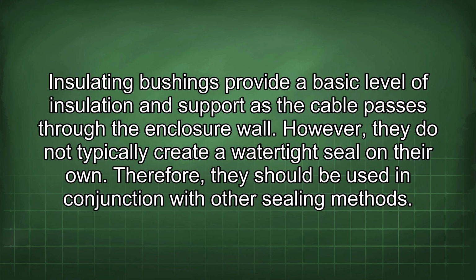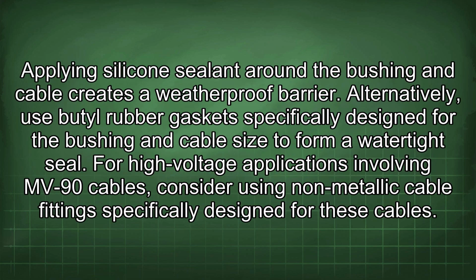However, they do not typically create a watertight seal on their own. Therefore, they should be used in conjunction with other sealing methods. Applying silicone sealant around the bushing and cable creates a weatherproof barrier. Alternatively, use butyl rubber gaskets specifically designed for the bushing and cable size to form a watertight seal.